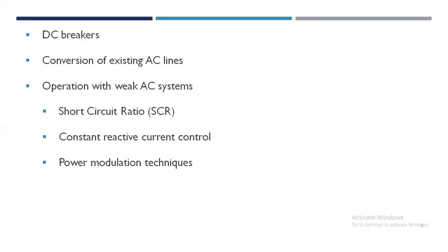Constant reactive current control or AC voltage control have been suggested to overcome some of the problems with weak AC systems. The use of fast reactive power control at the converter bus by applying static VAR systems is another alternative. Limiting dynamic overvoltages through converter control during load rejection is a standard practice. The power modulation technique used to improve the dynamic stability of the power system will have to be modified in the presence of weak AC systems. Coordinated reactive and active power modulation has been suggested to overcome the problems of voltage variation that can limit the effectiveness of power modulation.